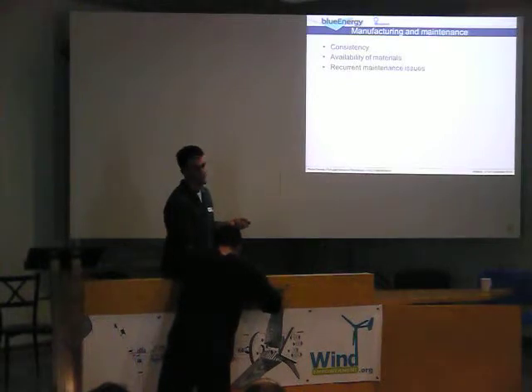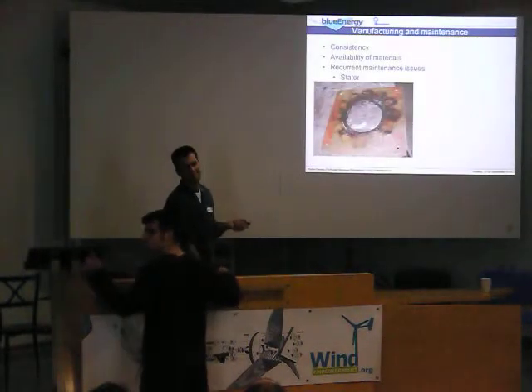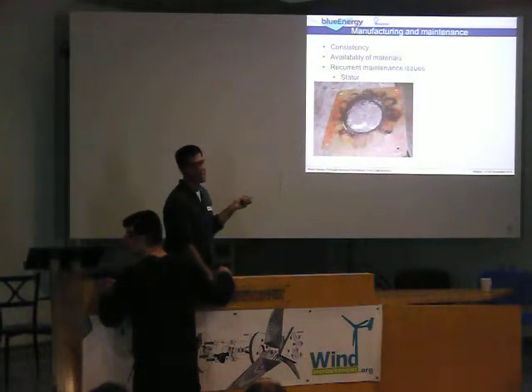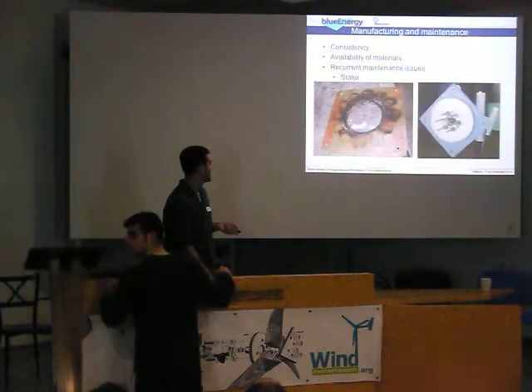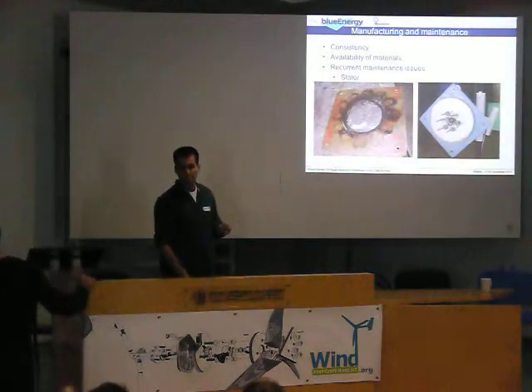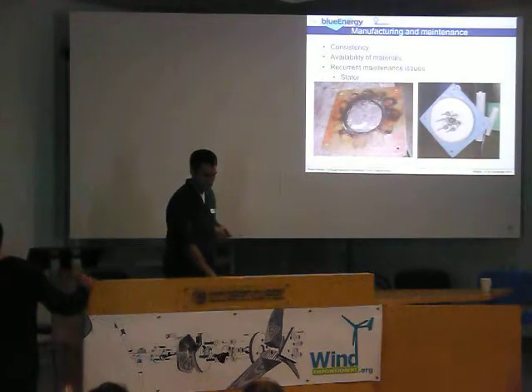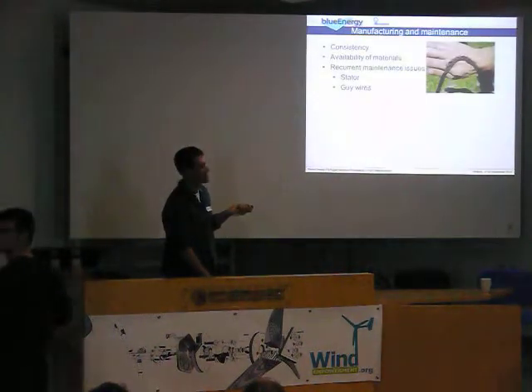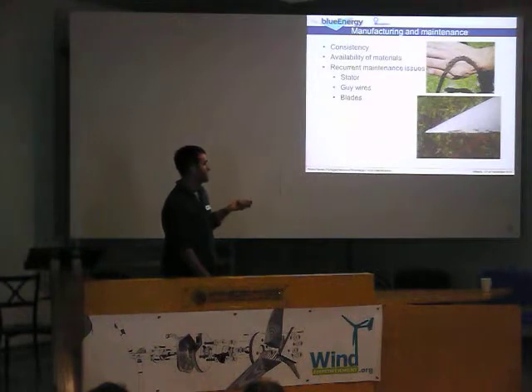For maintenance: stator burnout — too much current or a resin that doesn't dissipate heat properly. We solved that by using a different resin and some talcum powder to help dissipate heat. Guy wires — the same thing, we found a solution. Blade failures also. But we solved those problems.